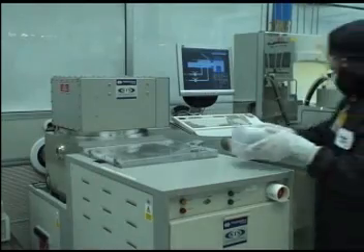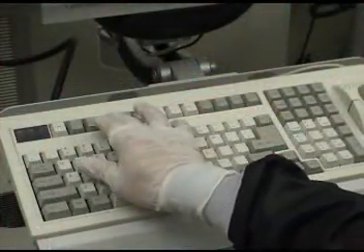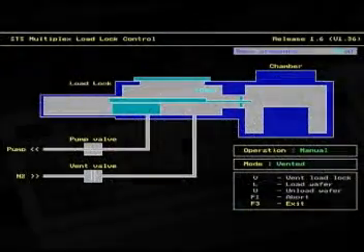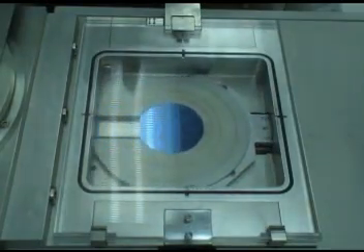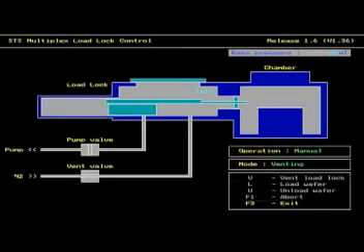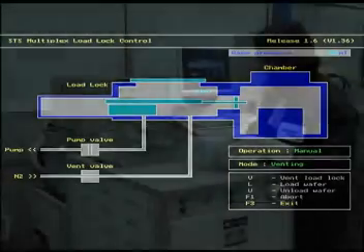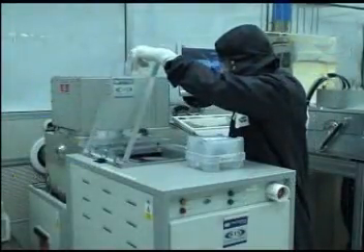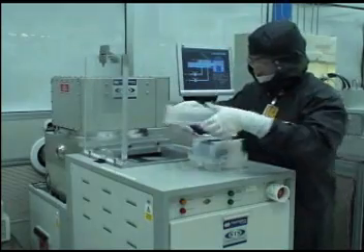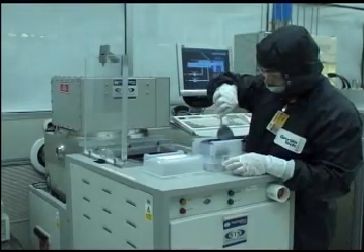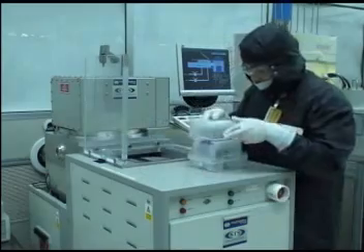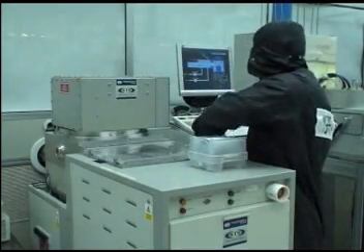Once the process is complete, you may remove your sample. Press the F3 button to access the load-unload feature, then press U to unload the sample. You will know that the load lock is vented when the chamber pressure reaches approximately 716 torr. At this point, the load lock may be opened and your sample can be removed.